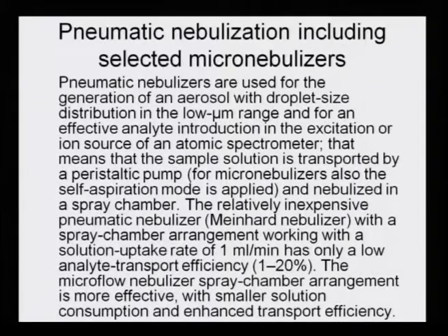The relatively inexpensive pneumatic nebulizer, or the Meinhard nebulizer, with a spray chamber arrangement working with a solution uptake rate of 1 ml per minute, has only a low analyte transport efficiency.